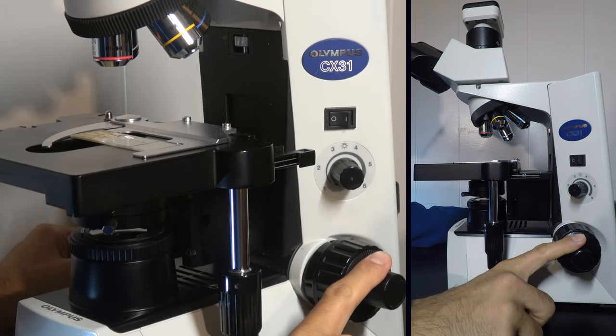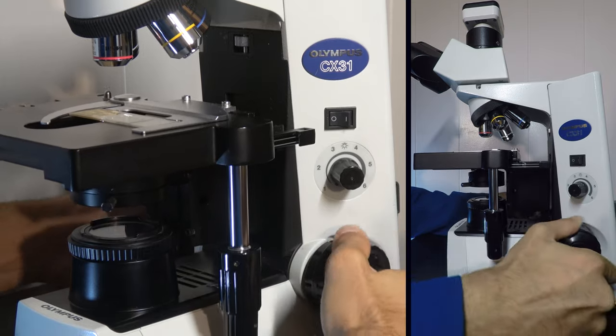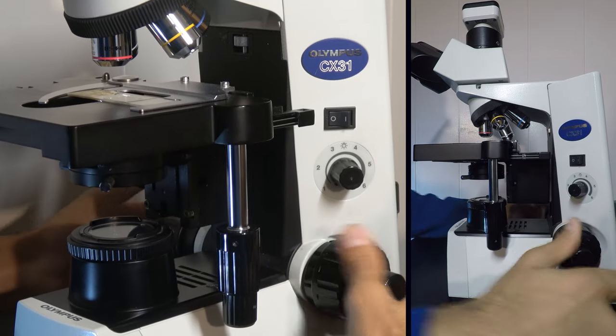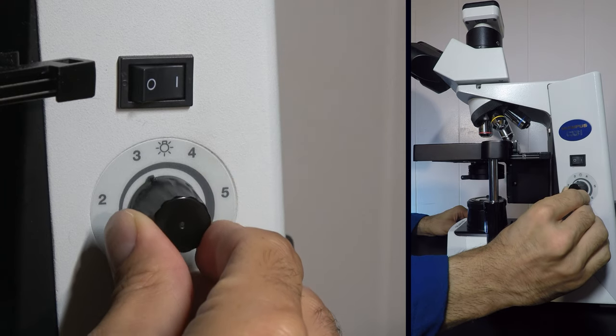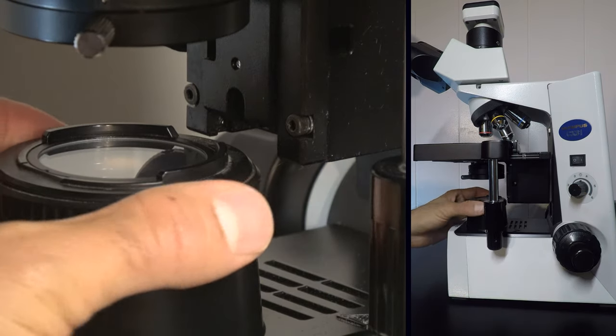Here is the fine focus knob but we will use the coarse focus first. Use both hands to slowly bring the stage to the top. Turn on the light and increase the intensity halfway to max. If adjustable, fully open the illuminator.